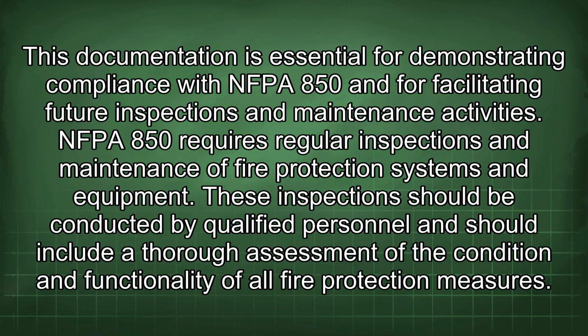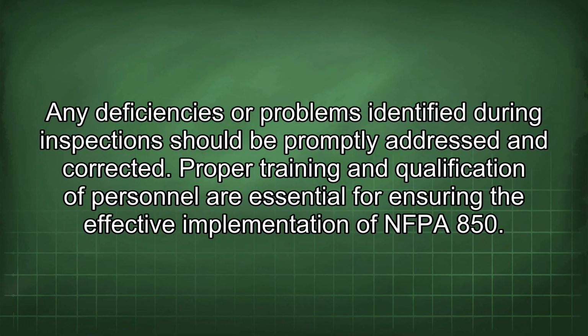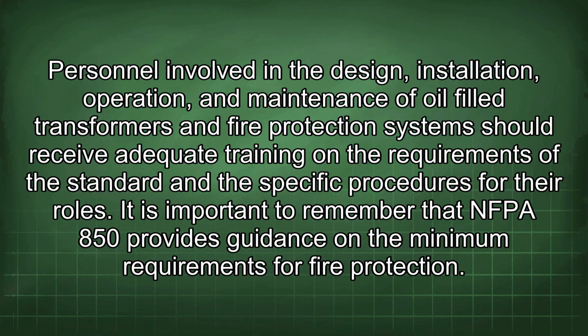These inspections should be conducted by qualified personnel and should include a thorough assessment of the condition and functionality of all fire protection measures. Any deficiencies or problems identified during inspection should be promptly addressed and corrected. Proper training and qualification of personnel are essential for ensuring the effective implementation of NFPA 850. Personnel involved in the design, installation, operation, and maintenance of oil-filled transformers and fire protection systems should receive adequate training on the requirements of the standard and the specific procedures for their roles.